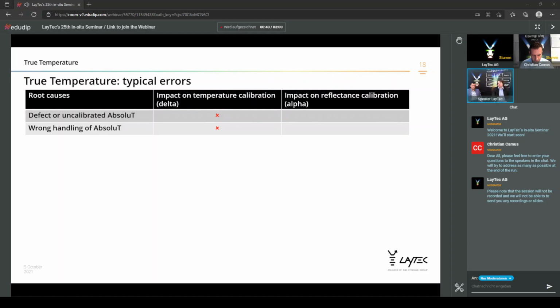So even though you would hold the AbsoluT right into the center axis of the viewport aperture, it still might lead to a wrong result in delta calibration if you don't hold the face plate or the face surface of the top cover of the AbsoluT flush to the opening, to the ceiling or to the reactor lid.